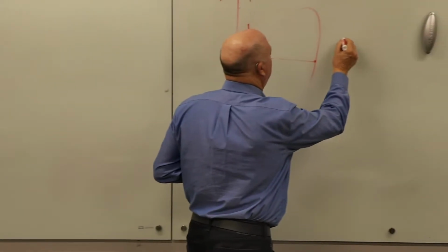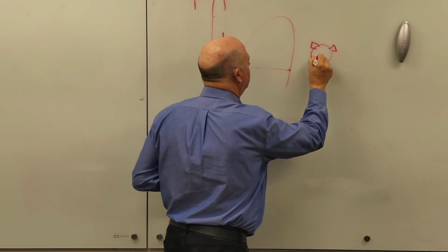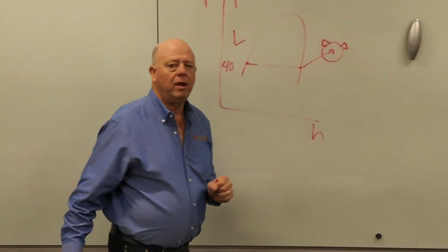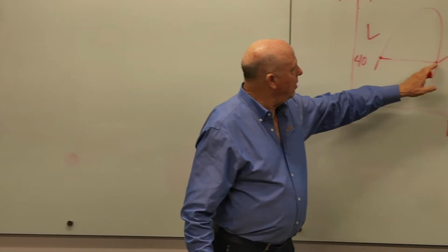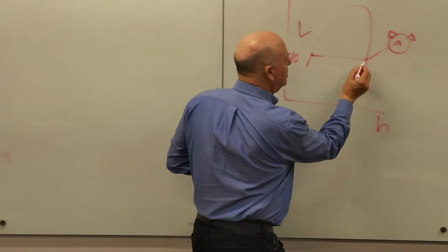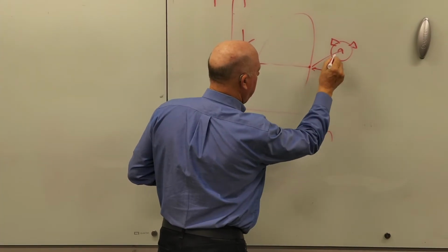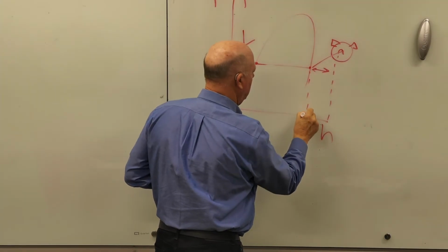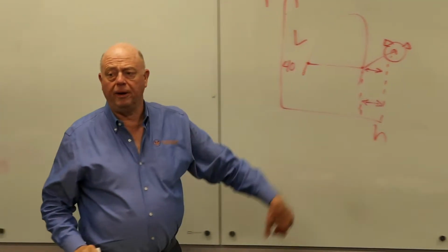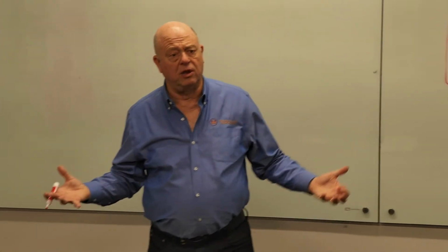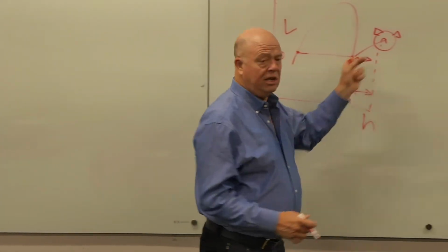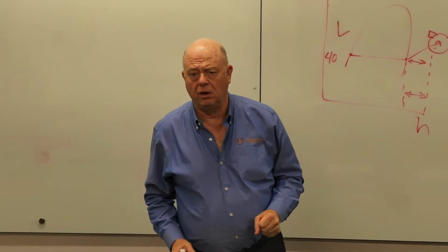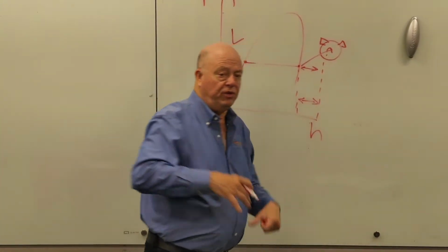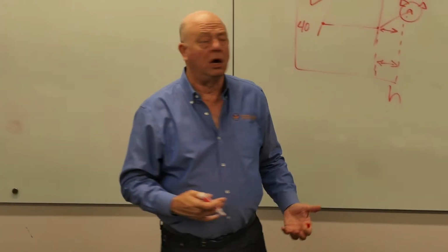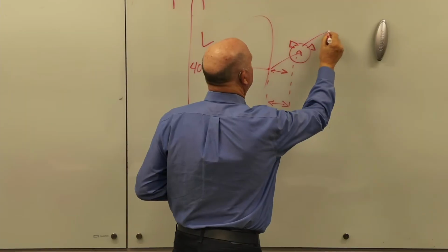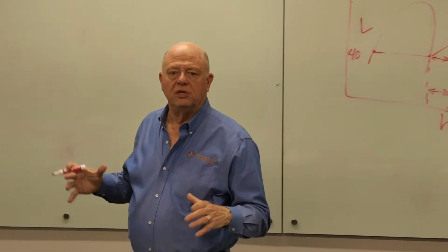And then there's going to be a compressor over here sucking up this gas, but you don't want to take it right off of here. You want this gas to move a little ways over to pick up some superheat. And the superheat is so we protect the compressor, because compressors break if they get liquid in them. Don't do well with it at all. And then off the discharge of the compressor will come the hot gas, and the compressor's role is a couple things.